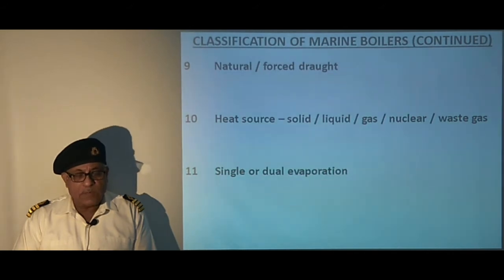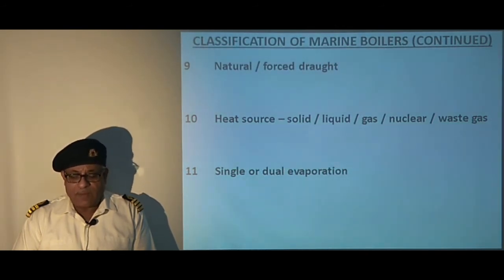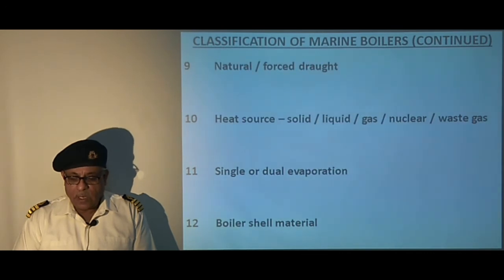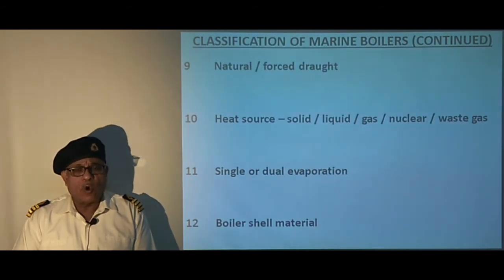As per steam evaporation — single or dual — most boilers have single evaporation, but when the risk of feed water contamination is high, double evaporation may be preferred. Lastly, we can classify the boiler as per material of construction. The shell of a modern boiler is constructed from steel, although very early boilers were made of wrought iron. Modern vessels have all-welded construction whereas earlier boilers had riveted construction.